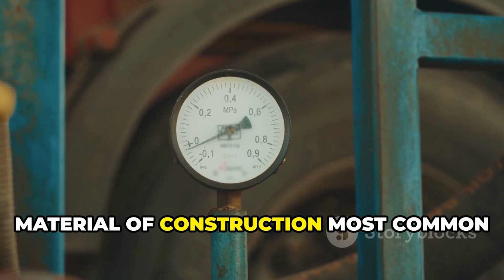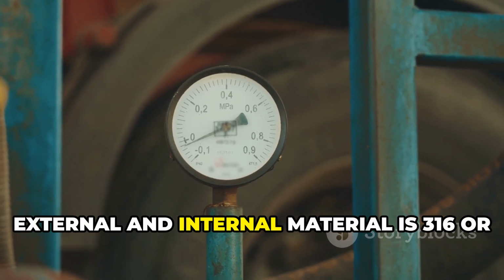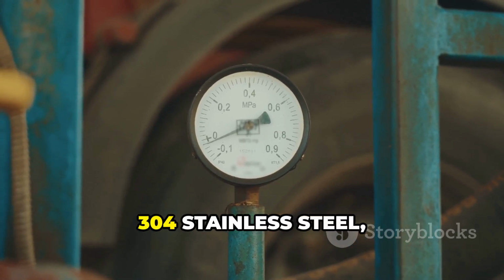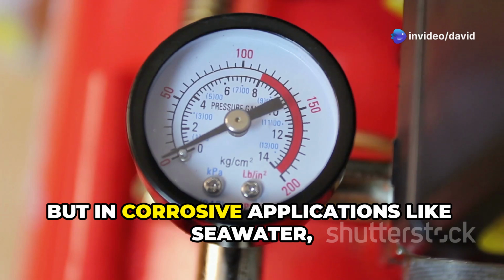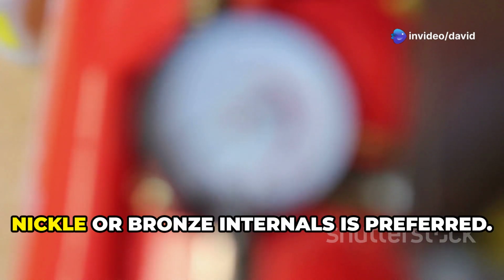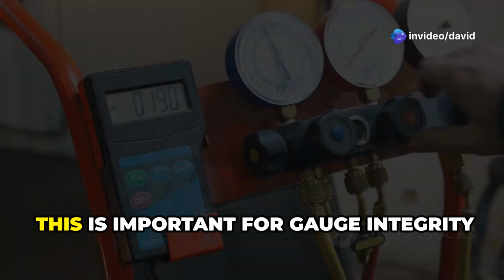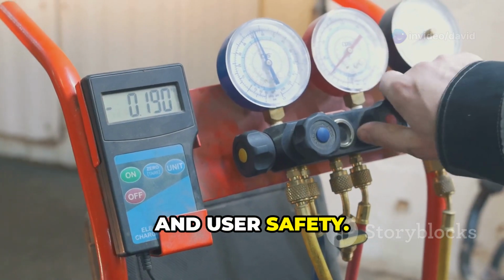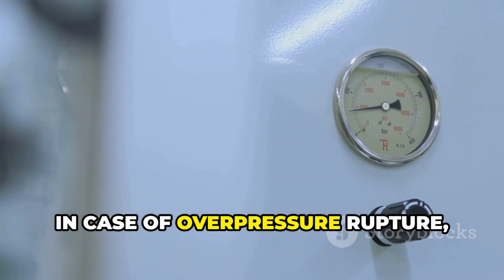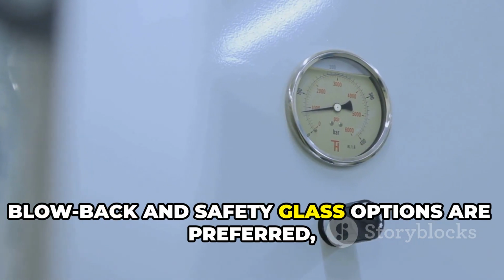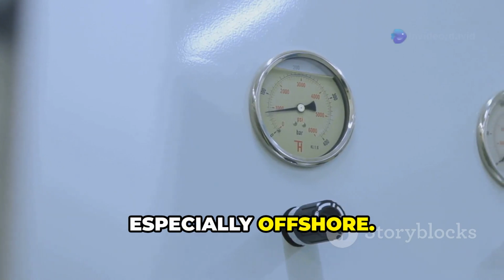Material of construction. Most common external and internal material is 316 or 304 stainless steel, but in corrosive applications like seawater, nickel or bronze internals is preferred. This is important for gauge integrity and user safety. In case of overpressure rupture, blowback and safety glass options are preferred, especially offshore.